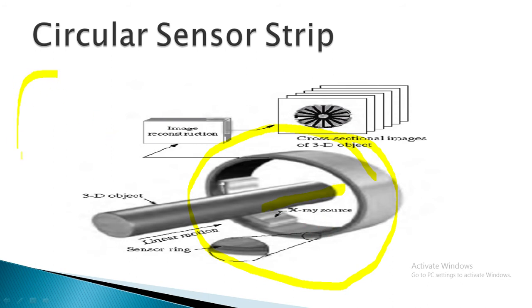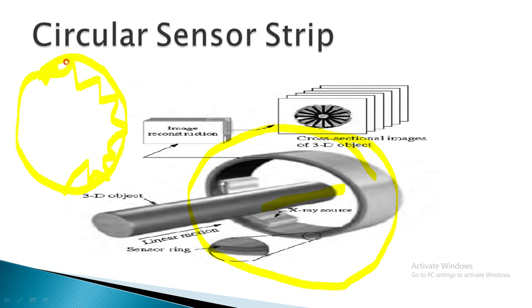We will be having a circular thing like this, and in this circular thing we will be having the sensors everywhere. Along with the sensors, we will be also throwing the x-ray light through this circular thing. Then you have a linear rod like this; this linear rod will be having a linear motion that is front and backward, and we will throw the x-ray light on this linear rod. Then that x-ray light will pass through the object on the linear rod and will be collected back by the sensors at the other end.